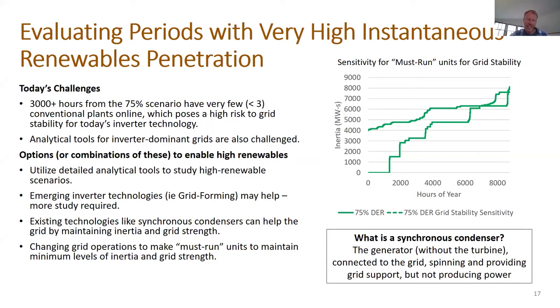A synchronous condenser, which is the generator end of a conventional power plant, can be used online without a turbine on the other end. So it's not consuming fuel or burning fuel. It's also not providing energy to the grid. But when it is connected, it is providing valuable grid services in terms of the inertia that we've discussed, as well as grid strength, which is important for other types of contingencies like the transmission contingencies I described.